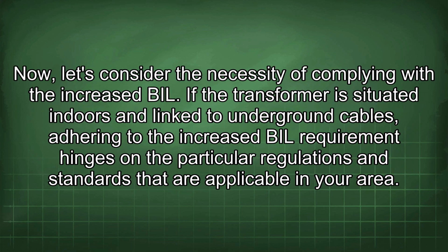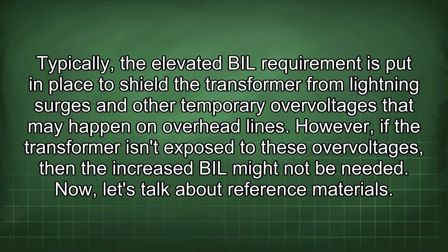Now let's consider the necessity of complying with the increased BIL. If the transformer is situated indoors and linked to underground cables, adhering to the increased BIL requirement hinges on the particular regulations and standards that are applicable in your area. Typically, the elevated BIL requirement is put in place to shield the transformer from lightning surges and other temporary overvoltages that may happen on overhead lines. However, if the transformer isn't exposed to these overvoltages, then the increased BIL might not be needed.